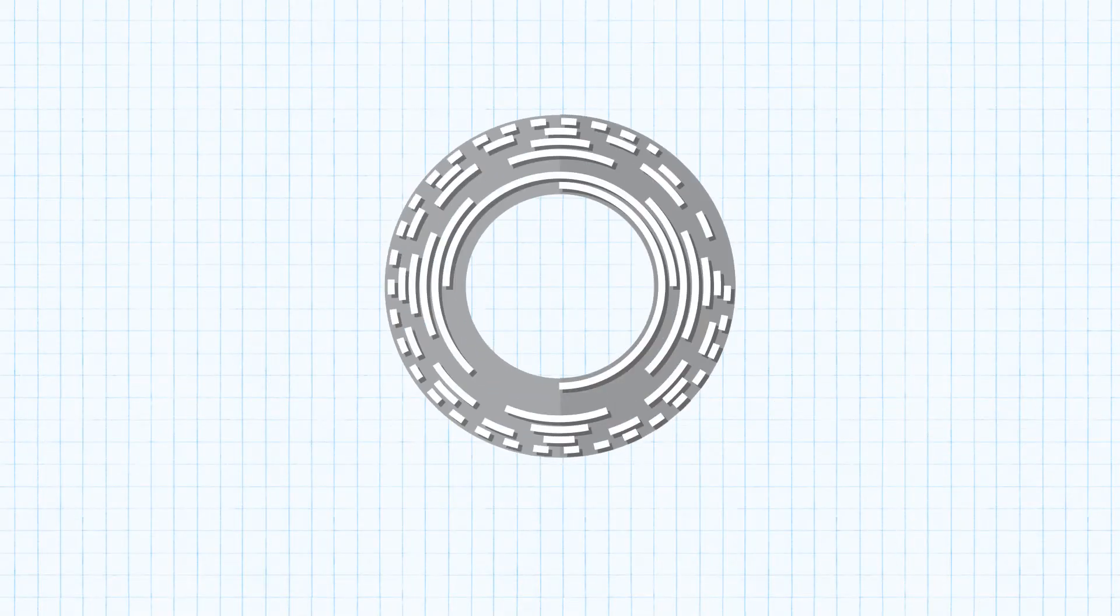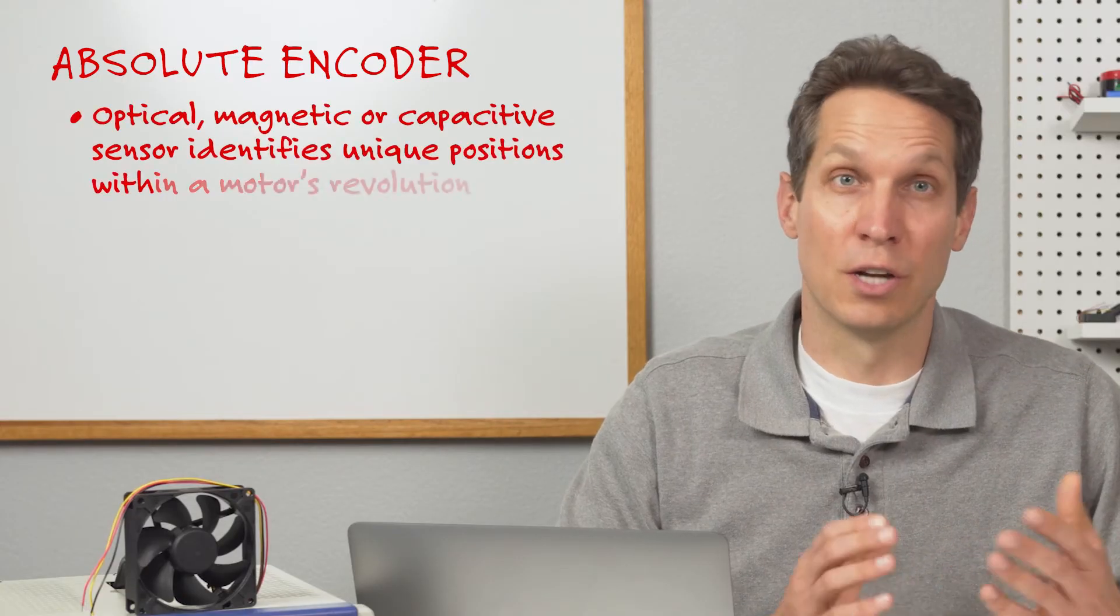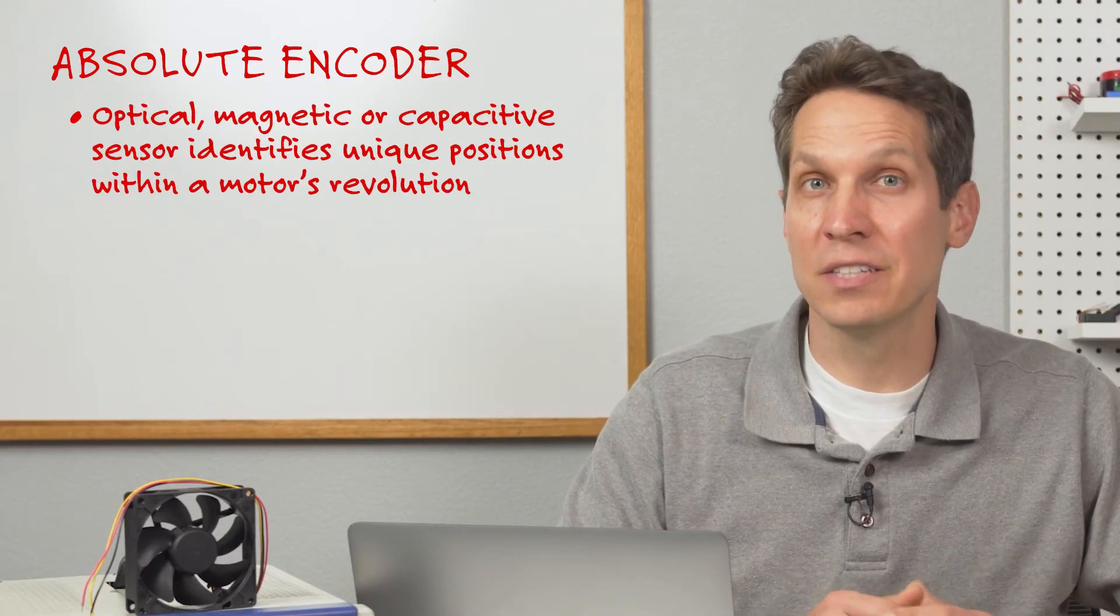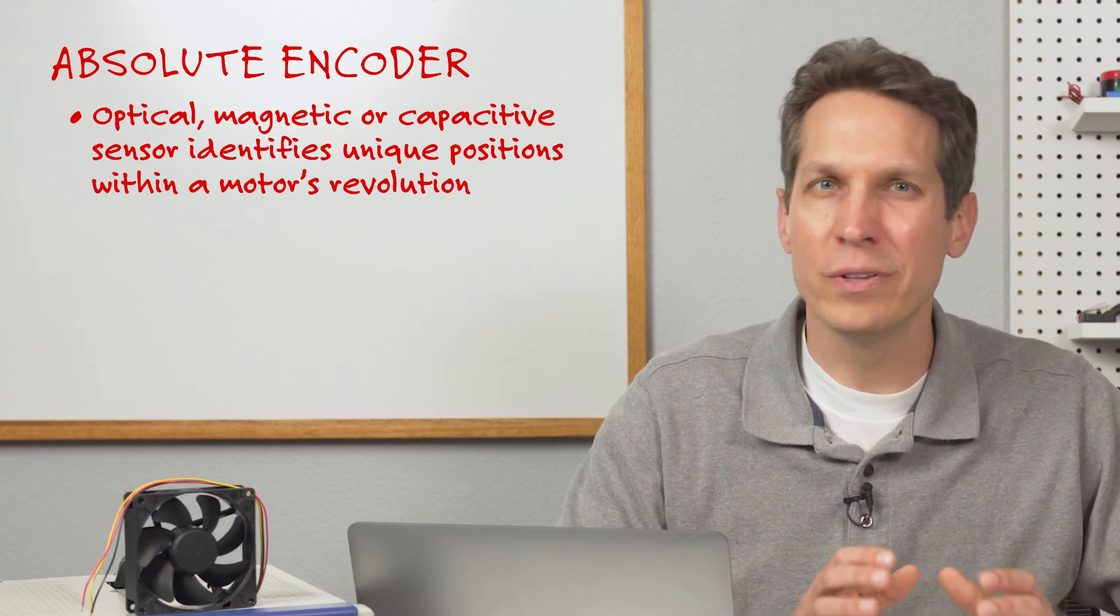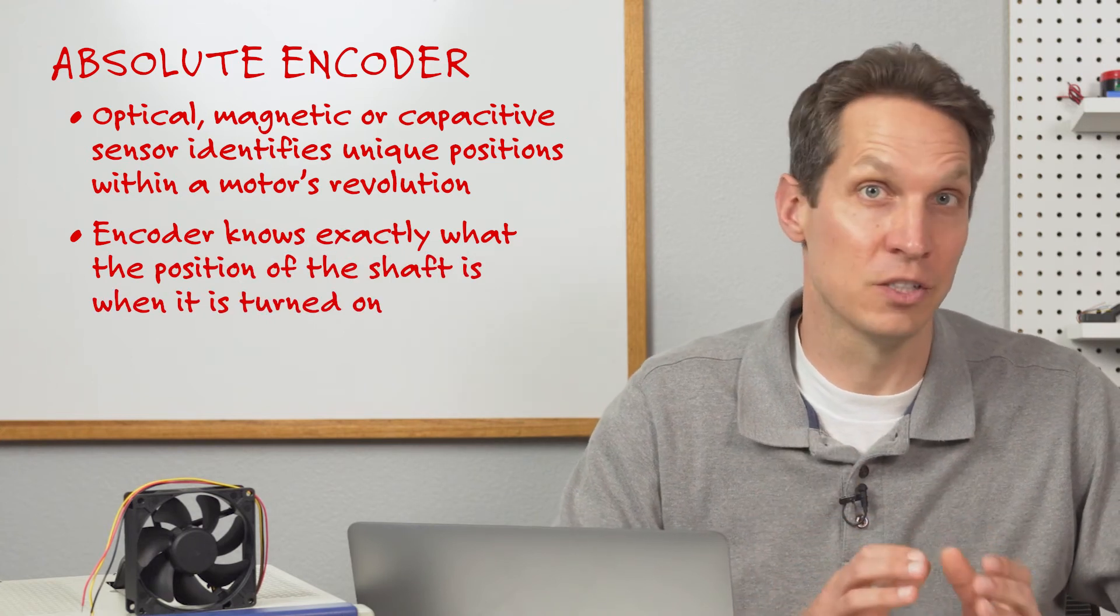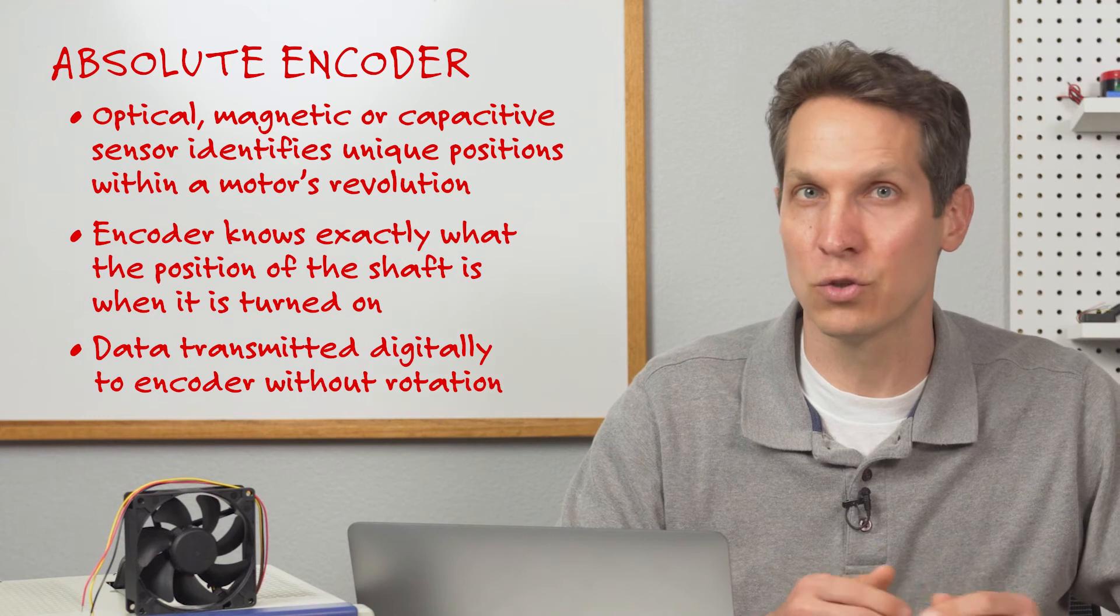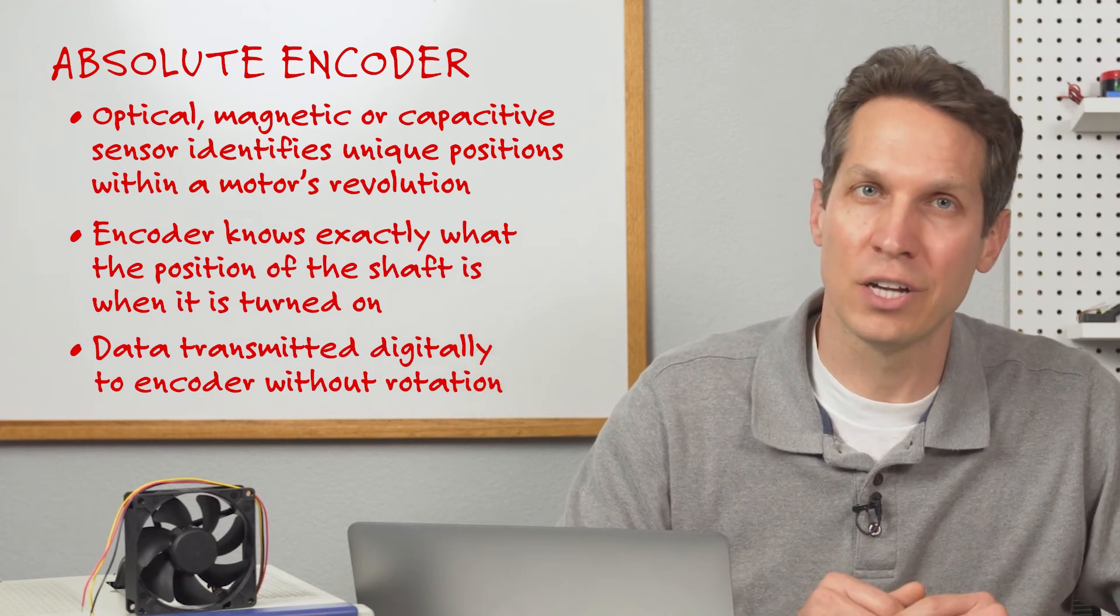However, all of these drawbacks are overcome with an absolute encoder. An absolute encoder uses an optical, magnetic, or capacitive sensor to identify unique positions within a motor's revolution. With these sensors, as soon as you switch on the encoder, it knows exactly what the position of the shaft is and will transmit that data digitally to your controller, usually over a serial interface, without needing to rotate the shaft.